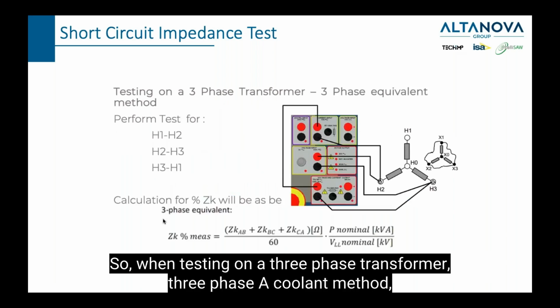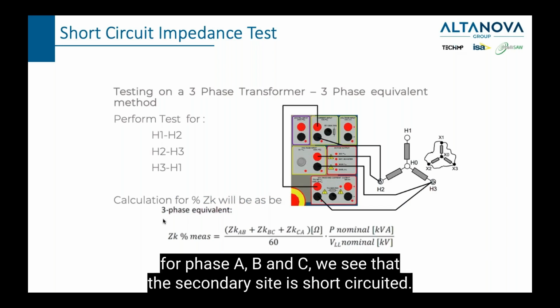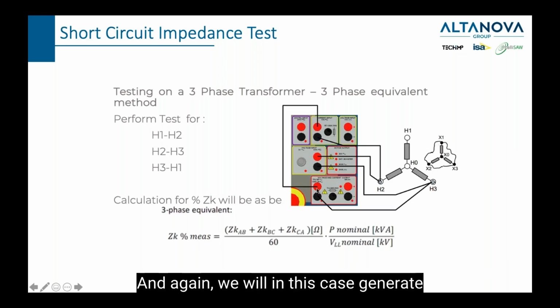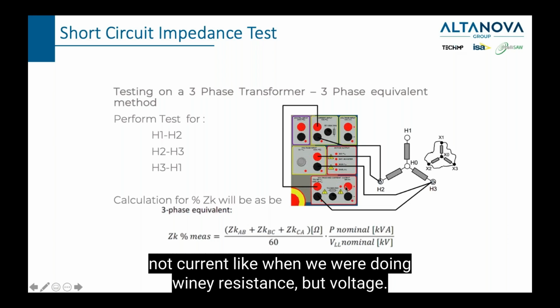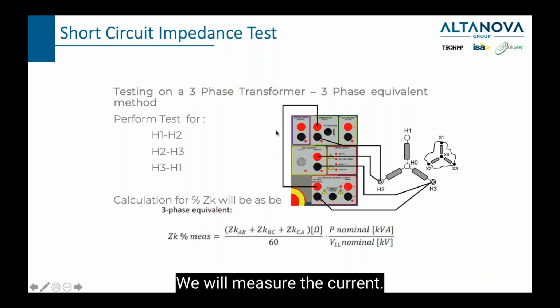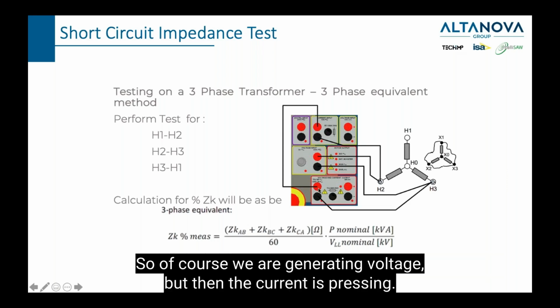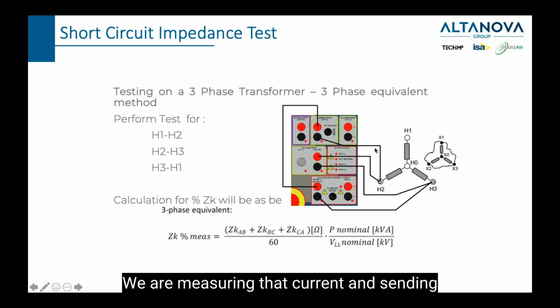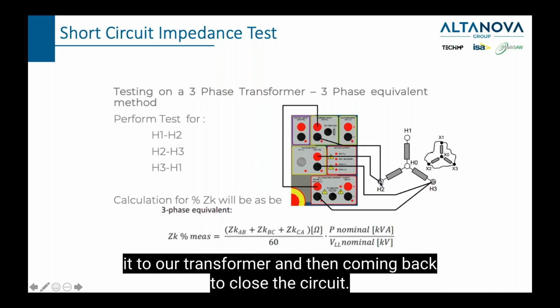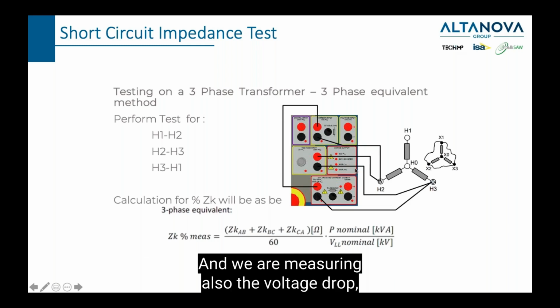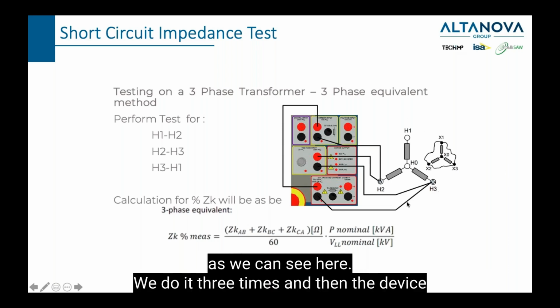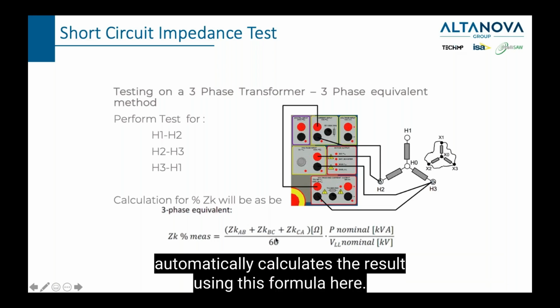So when testing a three-phase transformer with the three-phase equivalent method, we need to do three measurements, for phases A, B, and C. We see that the secondary side is short-circuited. And again, in this case we generate not current, like when we were doing winding resistance, but voltage. We measure the current. So of course we are generating voltage, but then the current is passing. We are measuring that current, sending it to our transformer, and then coming back to close the circuit, and we are also measuring the voltage drop, as we can see here. We do it three times, and then the device automatically calculates the result using this formula here.